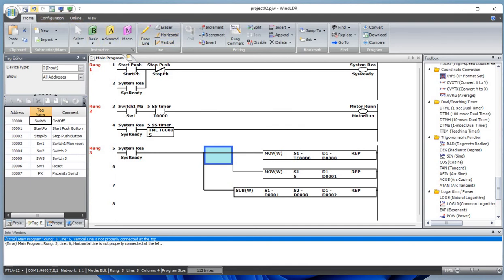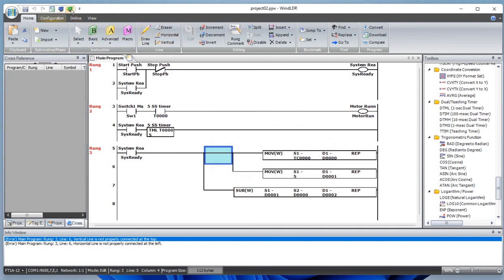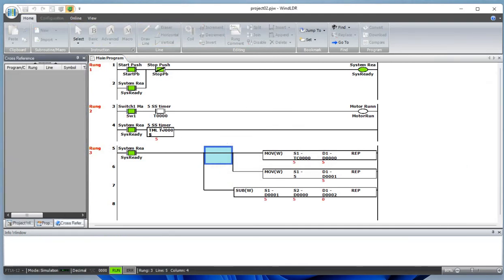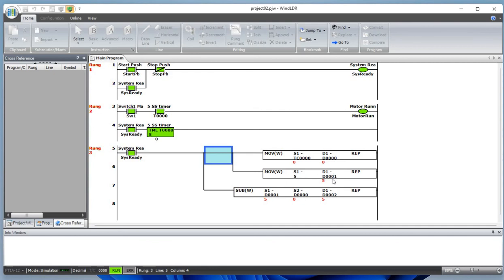Save this program. Let's simulate this. What happened is you see the data is moving from the current timer to data register zero. The preset value is moved to data register one, and the preset value minus current value is subtracted and saved on data register two.